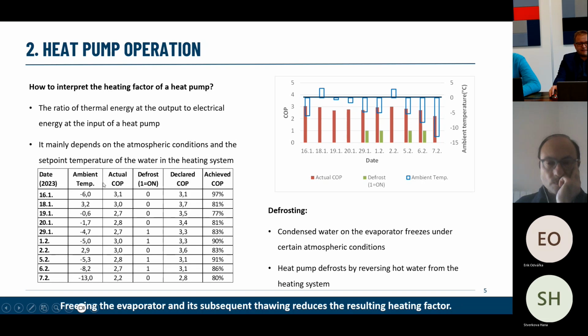So what you can read out of this data is what was the ambient temperature during the period. So as you can see, the very bottom was -13, so not favorable at all. You can see that the COP was just down to 2.2. So we had to deliver 1 kilowatt hour of electrical energy to draw 2.2 kilowatt hours of heat. On the other side, you can see that we've gone up even above 3 COP. So you cannot see the exact trend because it depends on what the heat pump does.